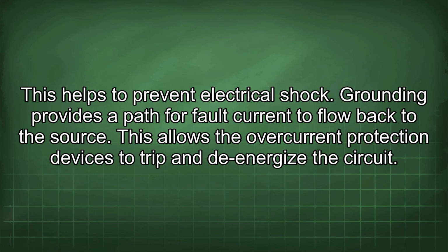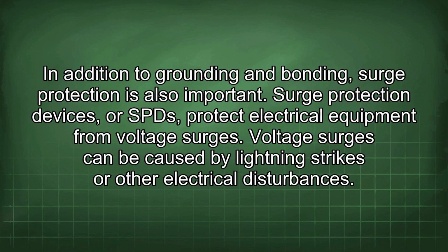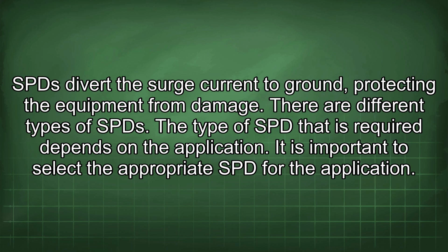Grounding provides a path for fault current to flow back to the source. This allows the overcurrent protection devices to trip and de-energize the circuit. In addition to grounding and bonding, surge protection is also important. Surge protection devices, or SPDs, protect electrical equipment from voltage surges. Voltage surges can be caused by lightning strikes or other electrical disturbances. SPDs divert the surge current to ground, protecting the equipment from damage.